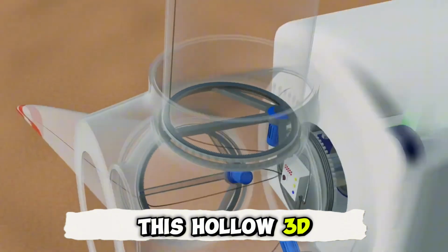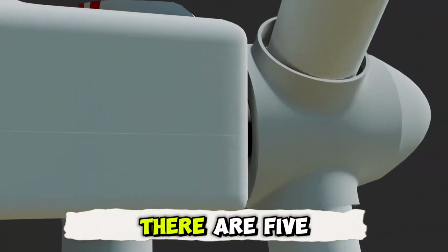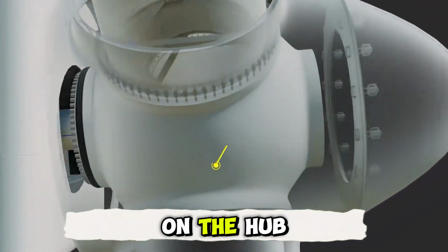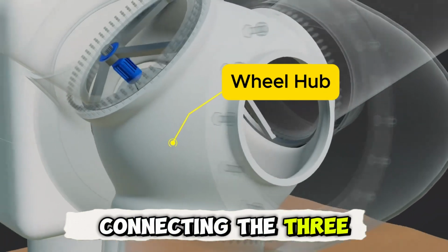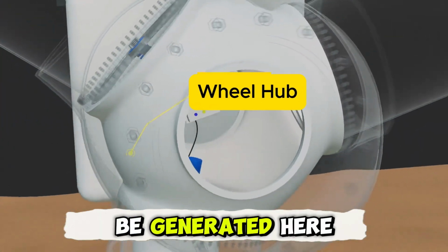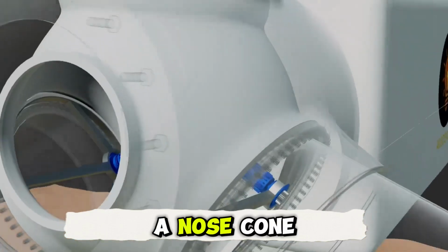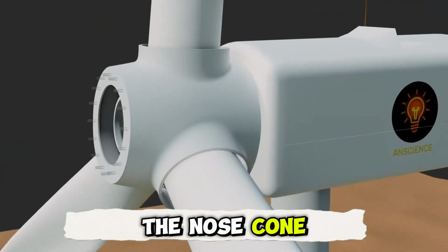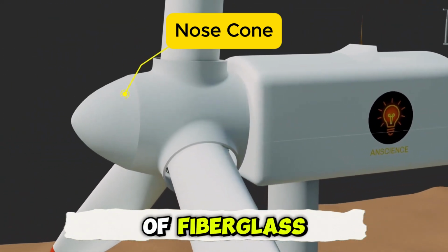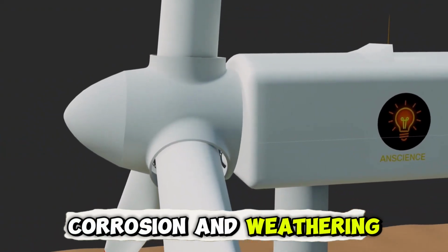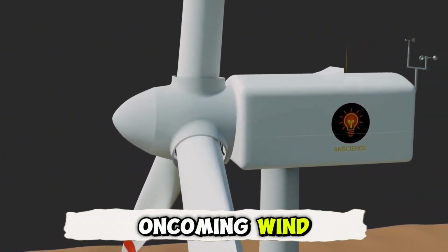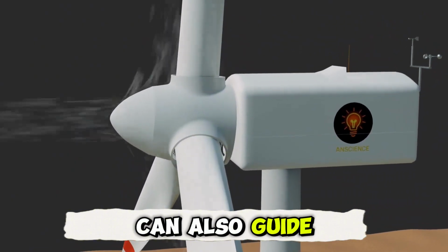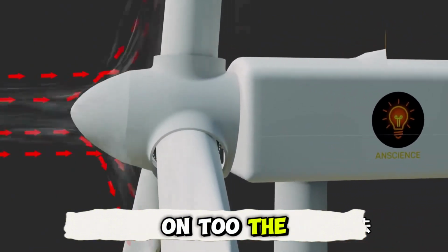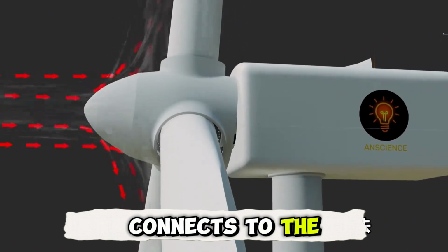This hollow 3D structure is the hub. There are 5 large circular holes on the hub. In addition to connecting the 3 blades, because resistance will be generated here at the front, a nose cone will be installed. The nose cone is usually made of fiberglass. It can prevent corrosion and weathering. At the same time, for the oncoming wind, the nose cone can also guide them better onto the blades. The circular hole at the back connects to the drive shaft.